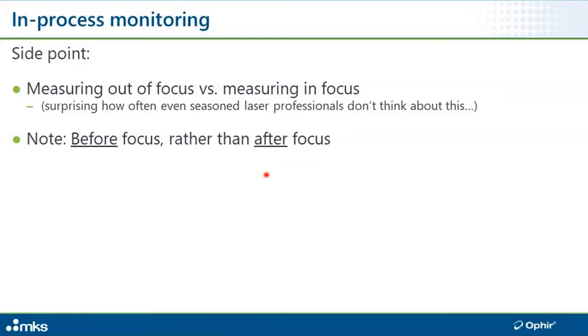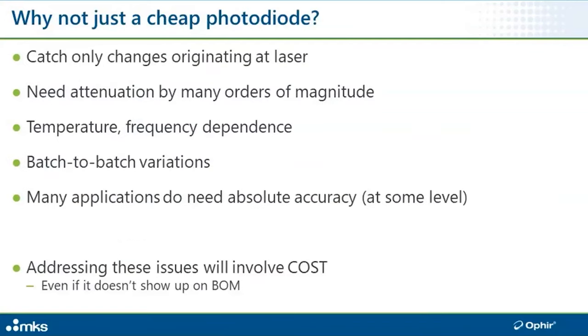Less known is that, all other things being equal, it's often preferable to measure before focus rather than after focus, as in the focal spot there are often losses caused by photoacoustic shockwave effects. The shorter the pulses, the more pronounced this effect can become. Just a very cool thing that I thought I would share with you.